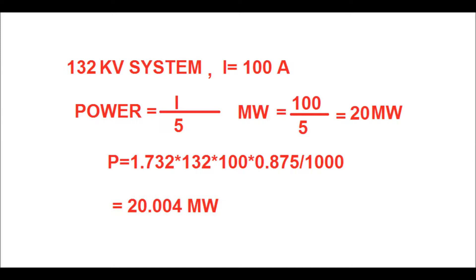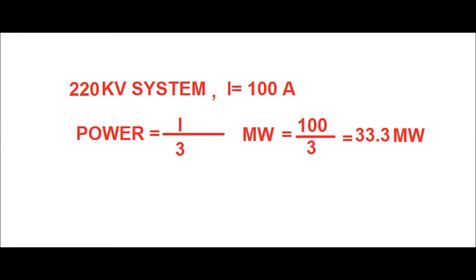...with power factor 0.875, divided by 1000 to get the value in megawatts, you get P = 20.004 megawatts. So the thumb rule for calculating power in megawatts for a 132 kV system is: whatever be the current, just divide by a factor of 5.